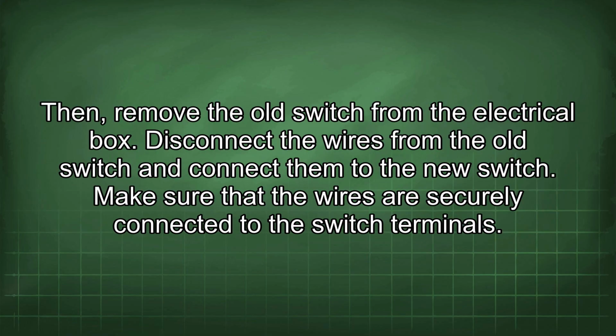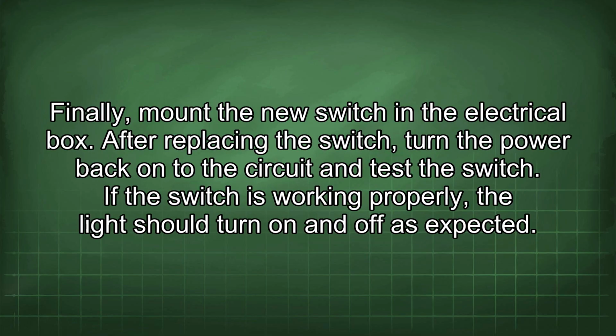Then remove the old switch from the electrical box. Disconnect the wires from the old switch and connect them to the new switch. Make sure that the wires are securely connected to the switch terminals. Finally, mount the new switch in the electrical box. After replacing the switch, turn the power back on to the circuit and test the switch. If the switch is working properly, the light should turn on and off as expected.